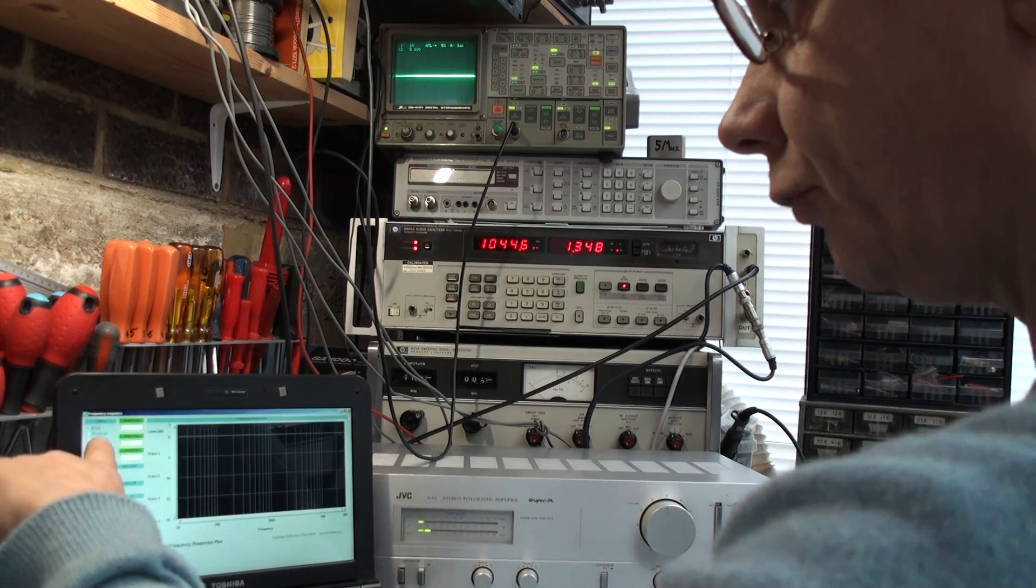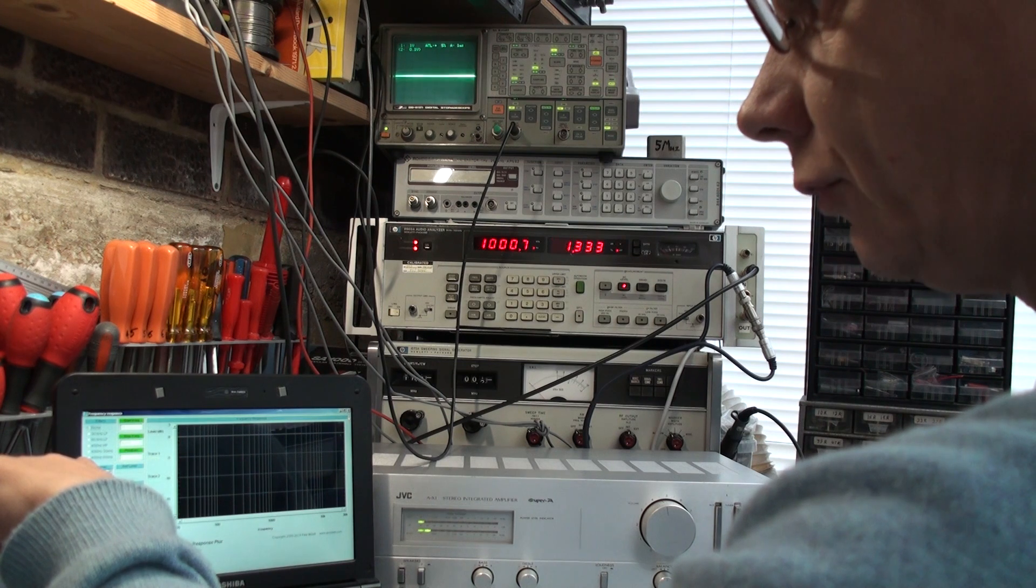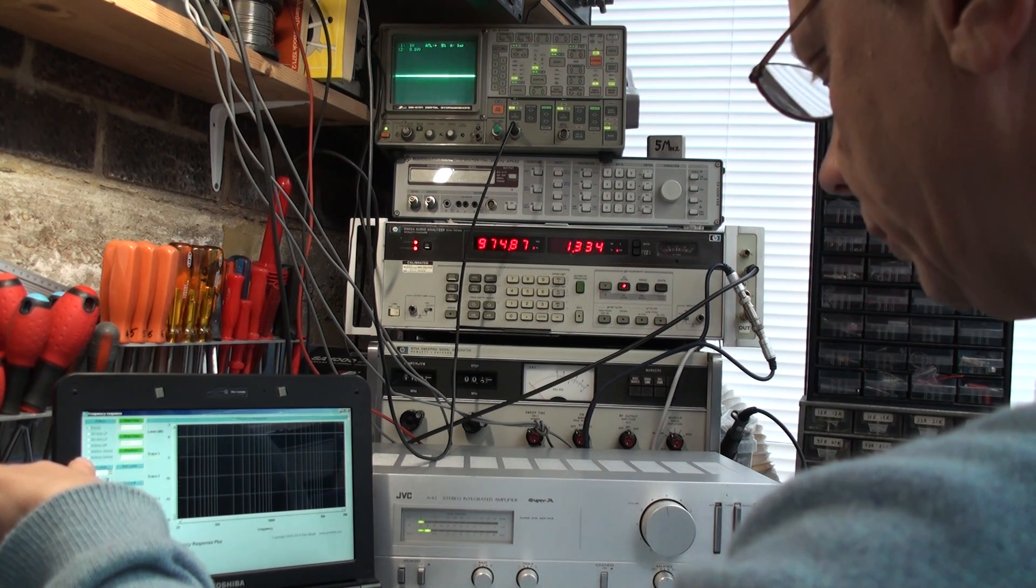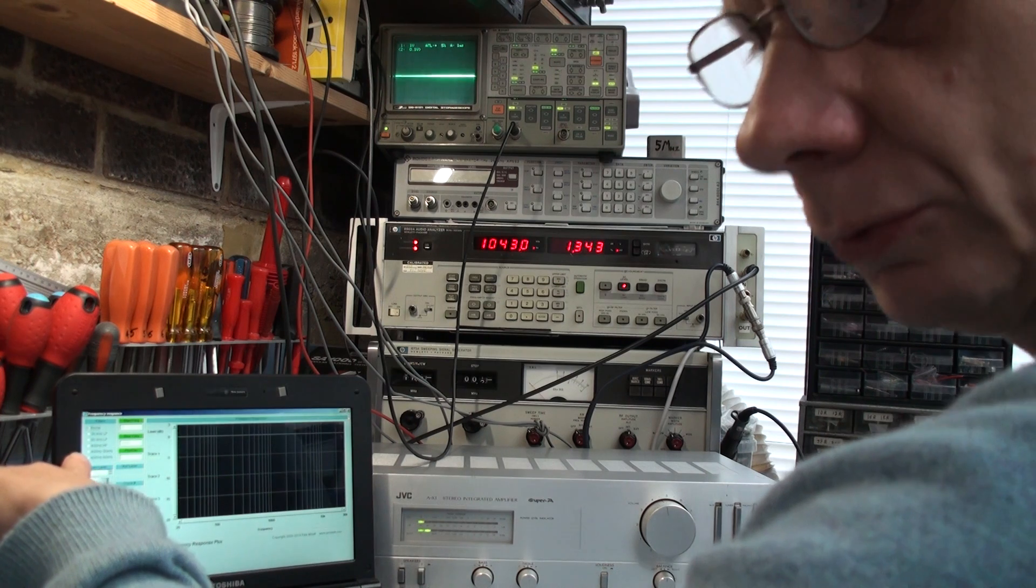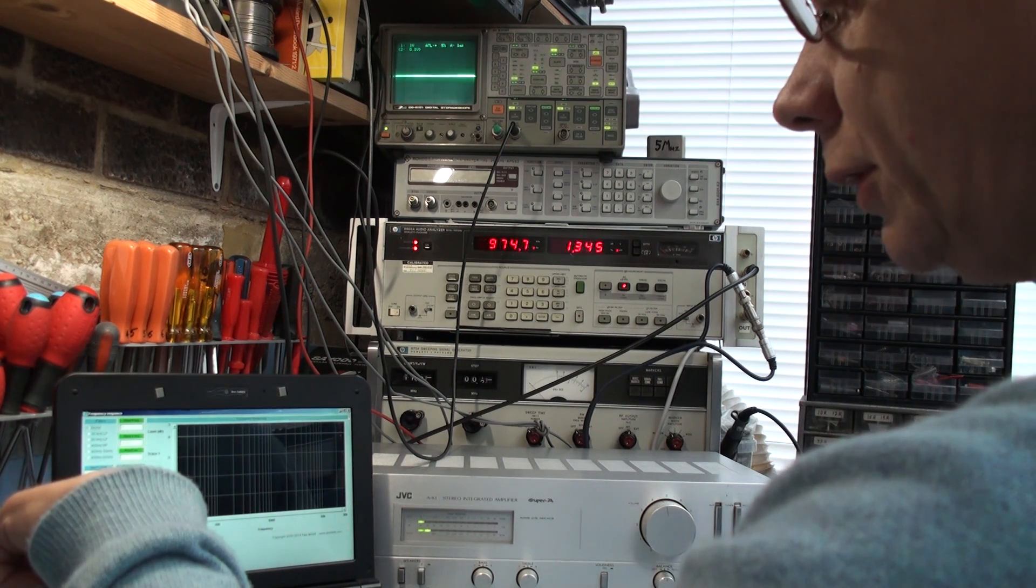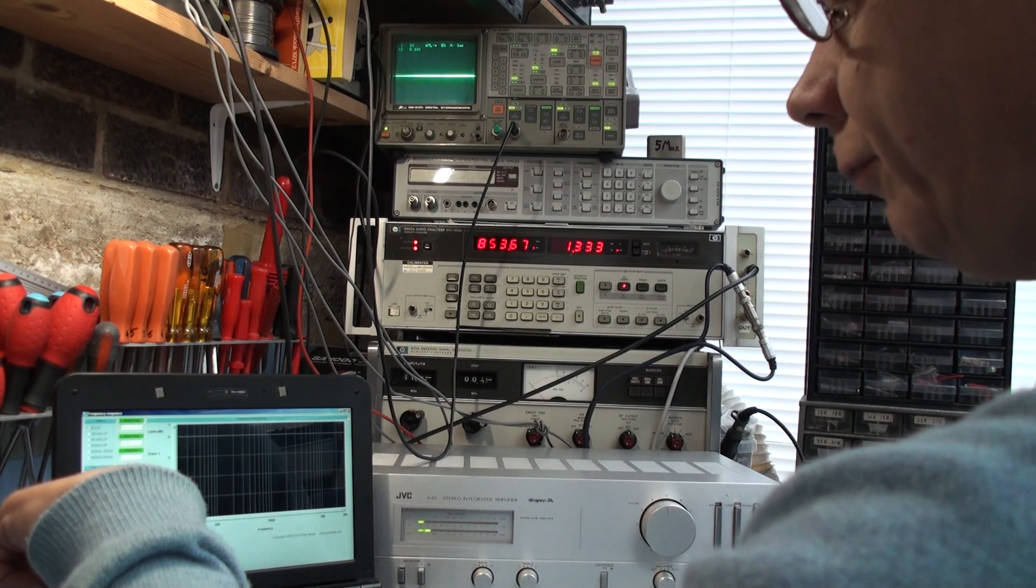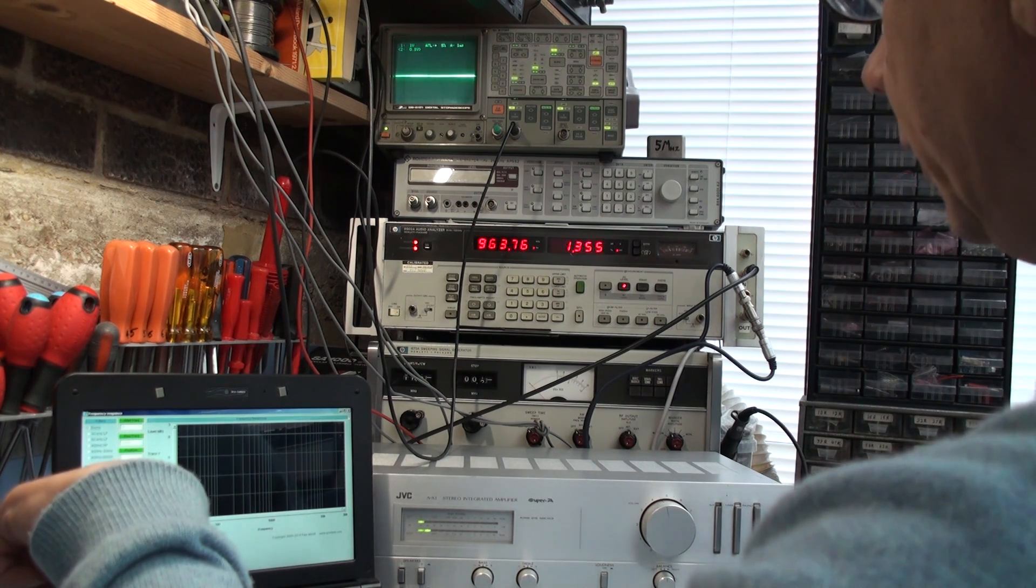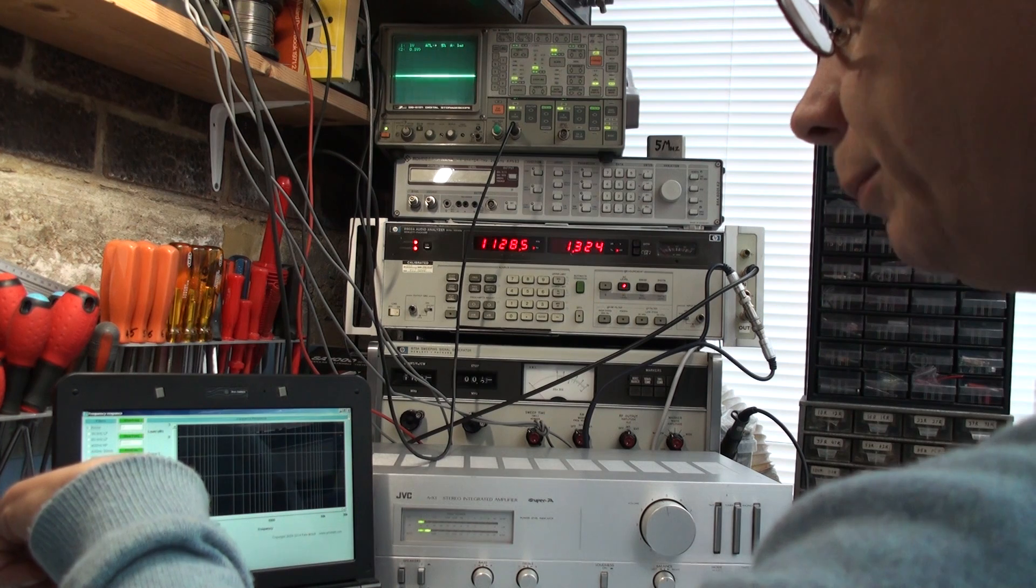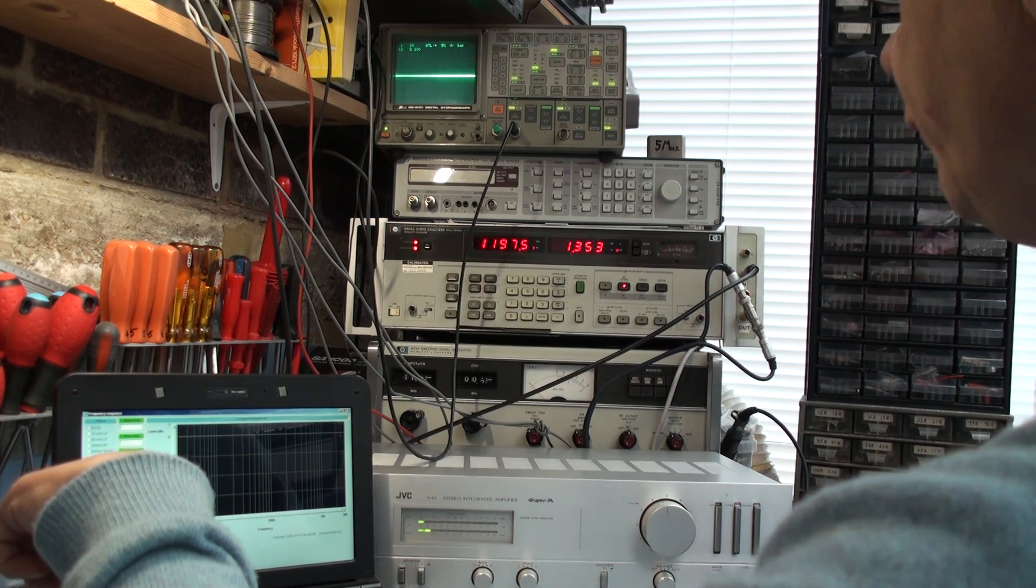Here we've got various options for allowing to enable filters, obviously if we're using frequency response we don't want to have any filters enabled at all. We've got this slider here allows us to adjust the reference level of the signal generator of the 8903, so that's our level point, and that's set at 1 volt, which is fine.